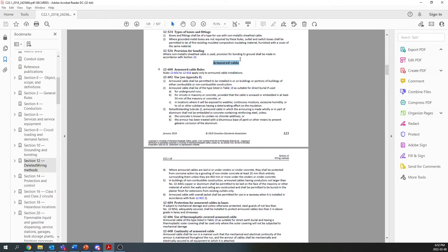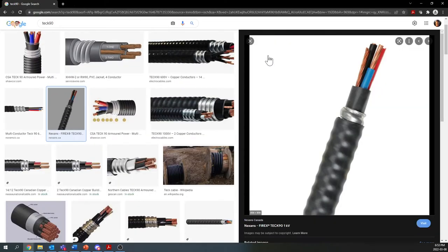For example, TECK90, as I was talking about, you can use it in all types of different situations. I may as well give you a picture here of TECK cable, as it's generally referred to. Okay, here. So here's a good picture. This is a three-conductor TECK90. You can see that it has the three interior conductors. It's got this extruded plastic sheath around those conductors. Whenever we say a three-conductor cable, the ground wire is always implied to be included. So you've got the interior plastic sheath, you've got the armor here, the wavy spiral wrap aluminum armor that I was talking about, and then you have an overall plastic sheath.